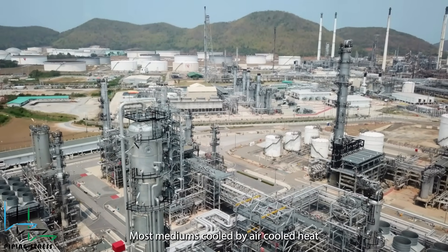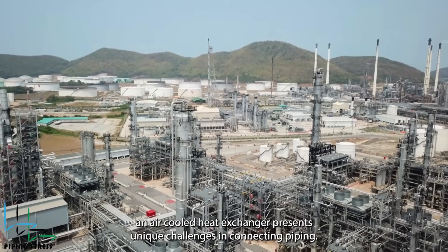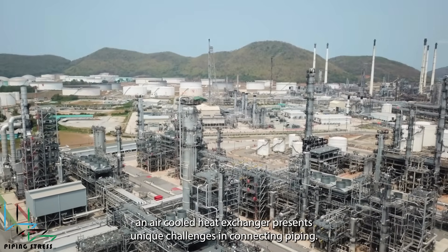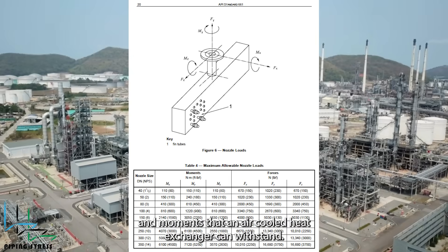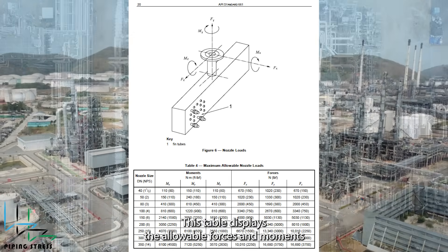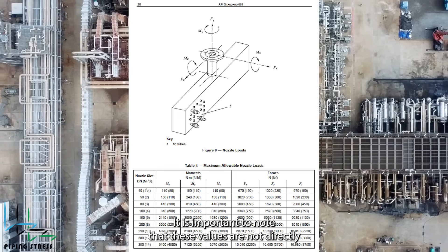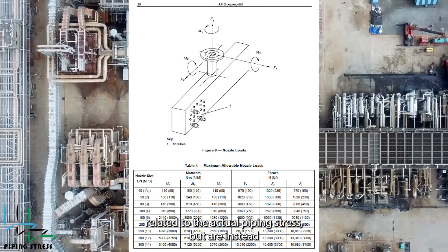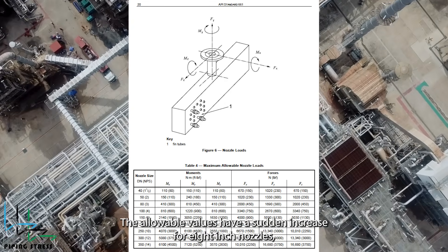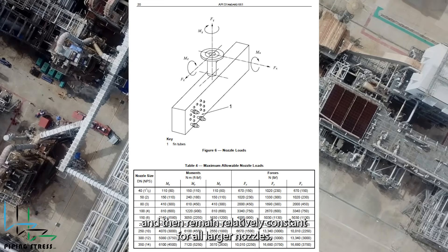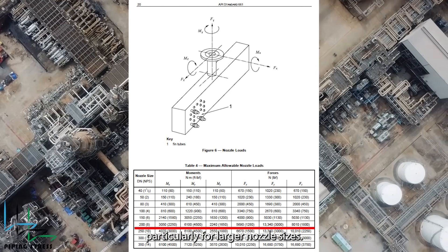Most mediums cooled by air-cooled heat exchangers are at low temperatures, and some are also at low pressure. As a result of its low temperature and pressure, an air-cooled heat exchanger presents unique challenges in connecting piping. The primary concern for piping engineers is the allowable forces and moments that an air-cooled heat exchanger can withstand. This table displays the allowable forces and moments for air-cooled heat exchanger nozzles as specified by API Standard 661. These values are not directly related to actual piping stress, but are instead based on practical and economic considerations. The allowable values have a sudden increase for 8-inch nozzles and then remain relatively constant for all larger nozzles; however, meeting these allowable values can be very challenging, particularly for larger nozzle sizes.